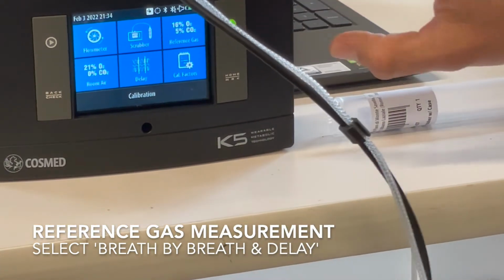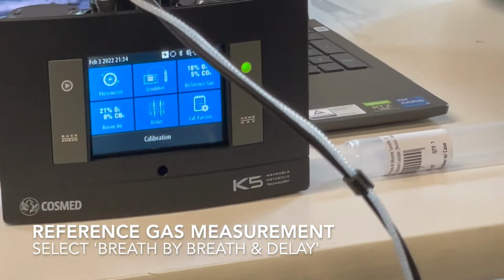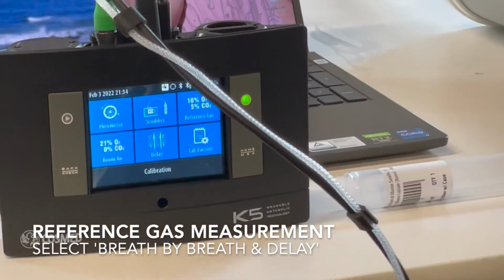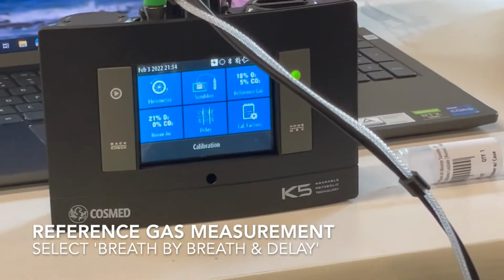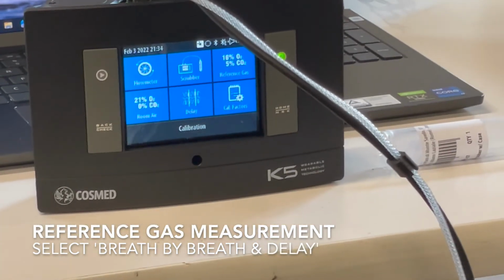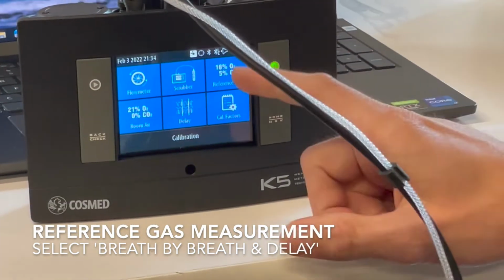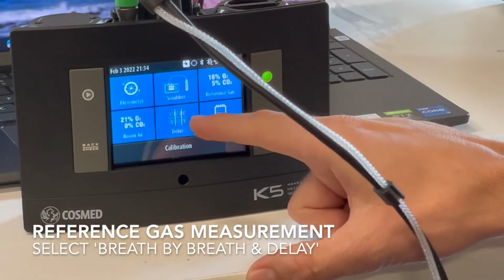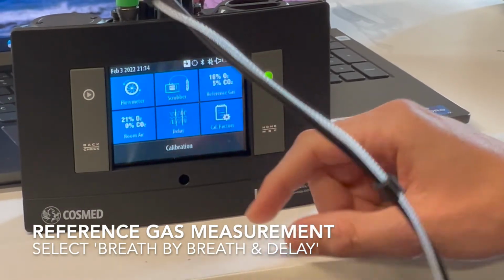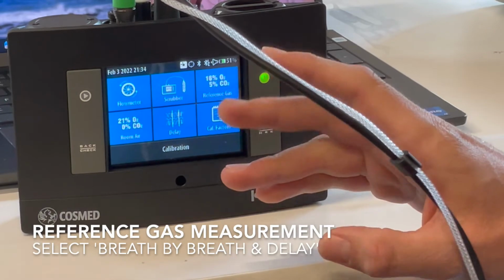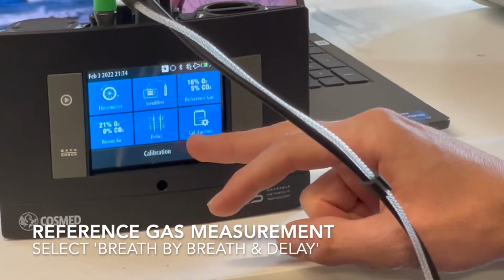The only thing is, if we're gonna calibrate in breath by breath, because it's gonna ask us when we do the gas cal, are you calibrating in breath by breath or are you calibrating in mixing chamber mode? If you do it in breath by breath, it's gonna automatically include the delay. So you don't need to do anything there. But if you're gonna do a mixing chamber test, you have to do the delay manually.